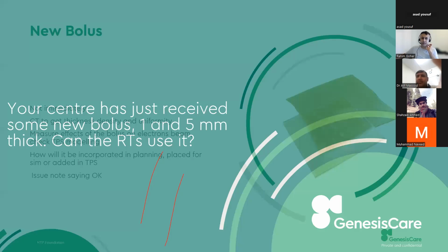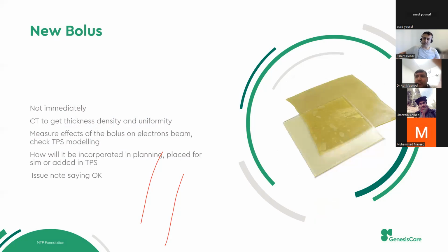So the answer was that you need to commission it. If it's water equivalent, take the readings in water, which is good. But the simplest way is to do the CT scan and check the thickness and the density. If there are no issues, then definitely we can use it straight away.